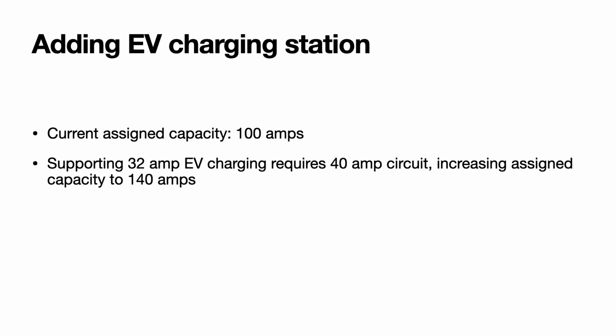So, adding an EV charging station. Suppose you calculated an assigned capacity of 100 amps. Supporting the 32 amp EV charging that would be fairly typical requires a 40 amp circuit, and therefore the assigned capacity has to go to 140 amps. That's straightforward. Now, the issue is whether the assigned capacity is more than the total capacity of the service panel, in which case you need to start thinking about a service panel upgrade.